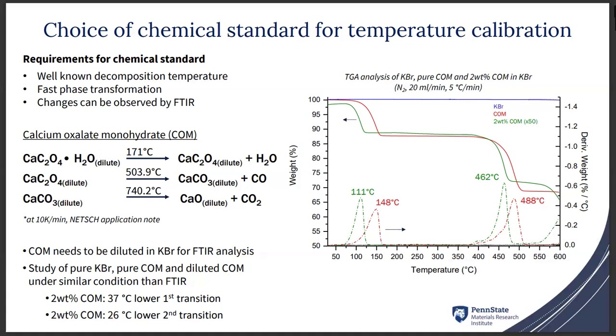So the first step was to analyze those materials using TGA. We first analyze the pure compound using parameters that we will use later on for the FTIR: nitrogen, a flow of 20 milliliters per minute, and a ramp of 5 degrees Celsius per minute. We analyzed the pure calcium oxalate monohydrate, and we saw the first event at 148 Celsius and the second event at 488 degrees Celsius. And then we decided to look at the diluted sample because by FTIR we want to use a diluted sample to avoid saturating the detector.